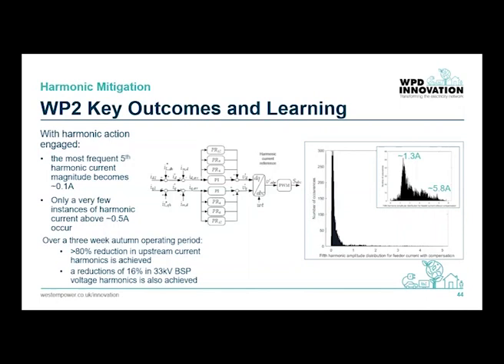Very similar results are achieved for the 7th, 11th and 13th harmonics. Our assessment of the controller's impact over a 3-week period was that there was more than an 80% reduction in upstream current harmonics and a 16% reduction in voltage harmonics at the upstream busbar. With more inverters operating with this type of controller, we believe that this impact will be greater, but that is the subject of the next work package.